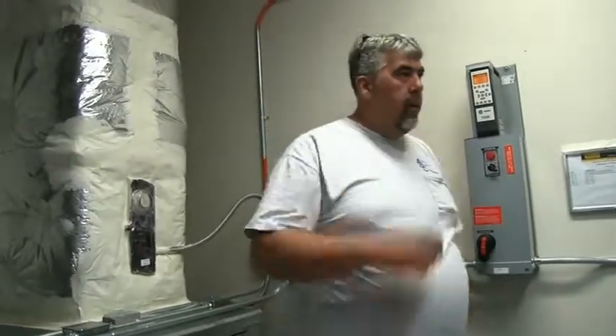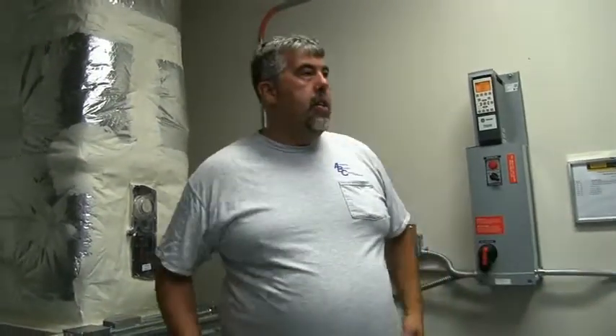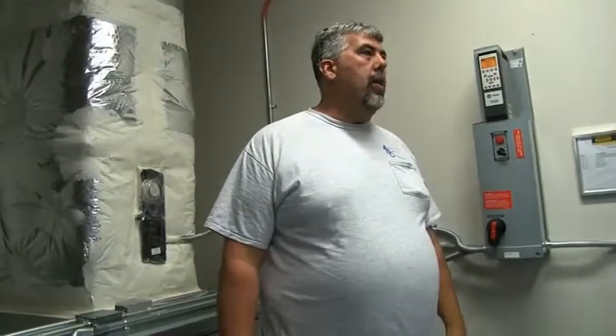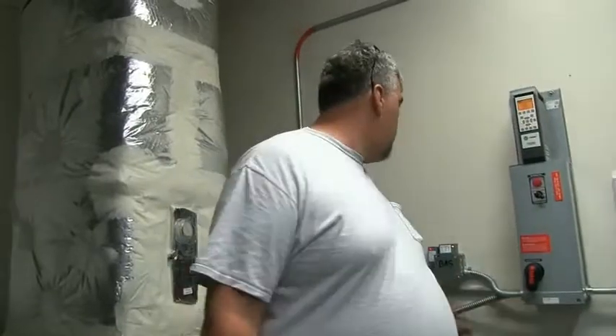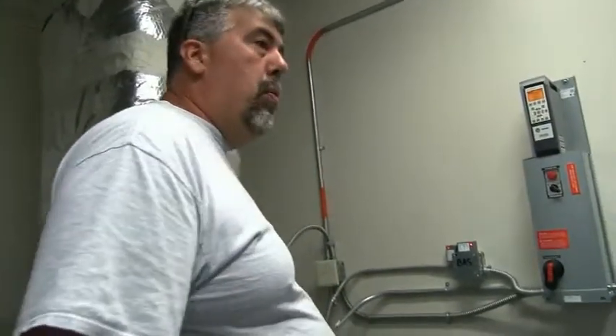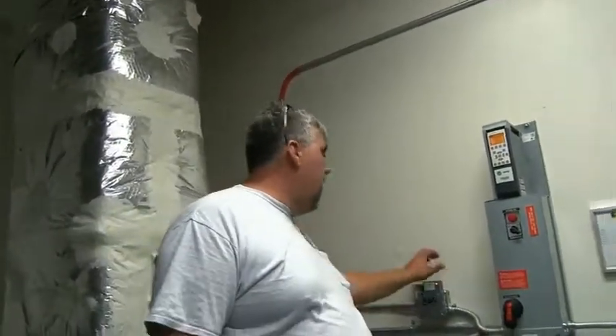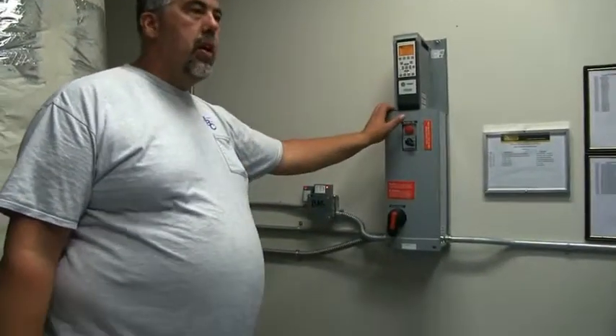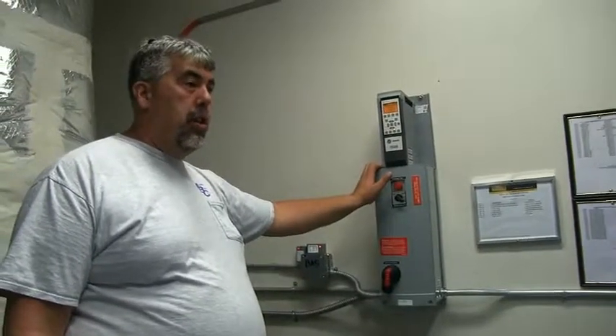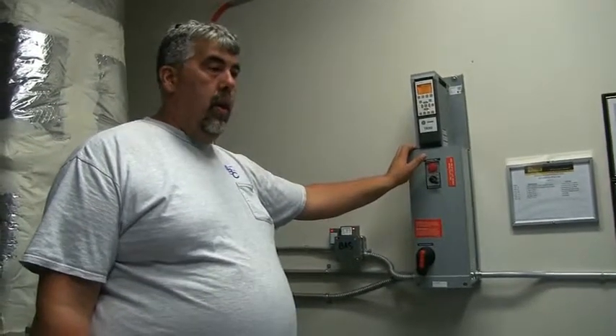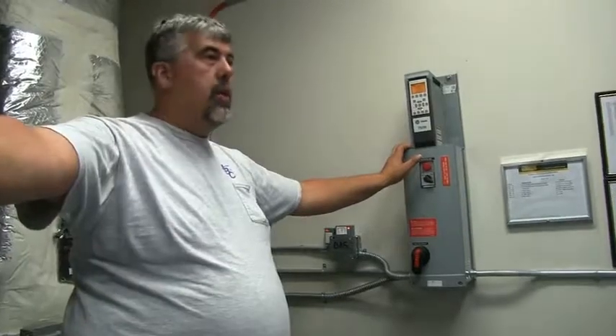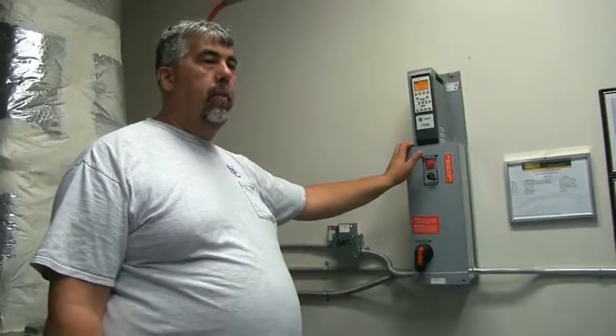When you guys wired them, is that a dry set of contacts? It's got 24 on it, but it's dry. And how it works is it takes one leg of the 24 volts that comes over to this relay over here, and it goes through the dry contacts. If either one of these dry contacts breaks, it breaks this relay, which breaks the safety circuit in here, which shuts the drive off. Right, and the 24 is fed from? It's fed from a transformer underneath the controller over there.